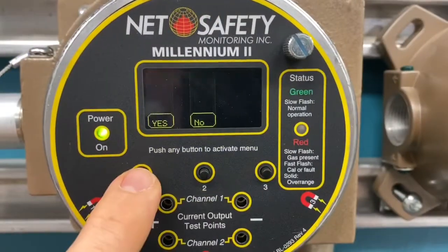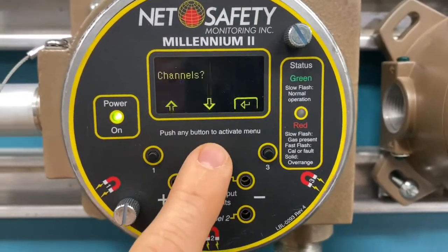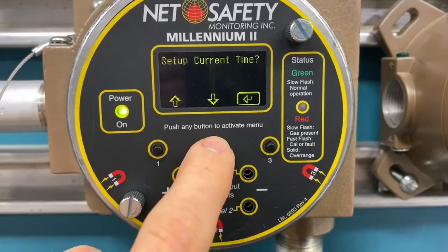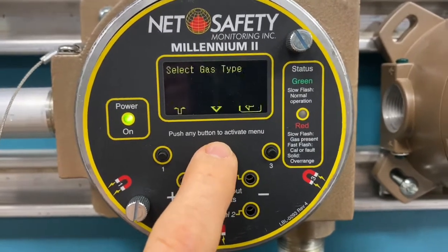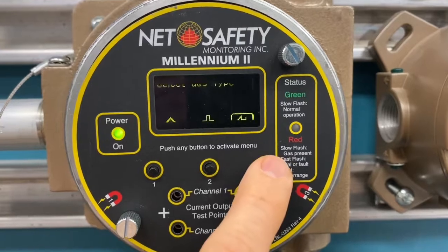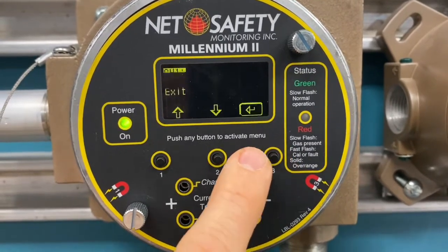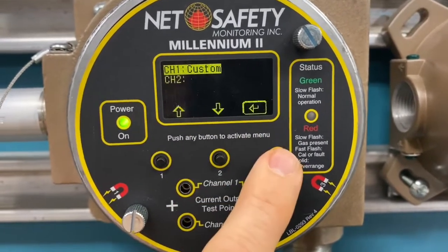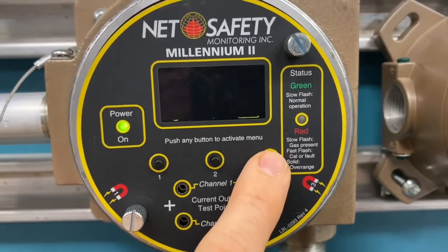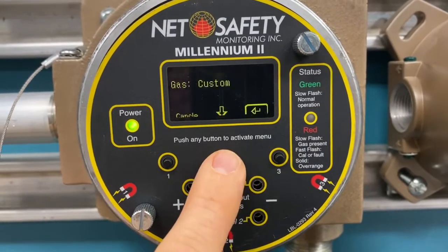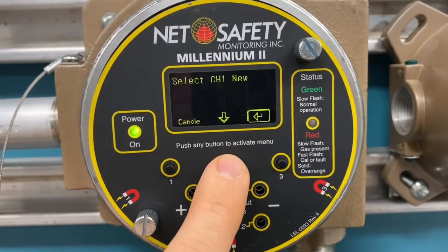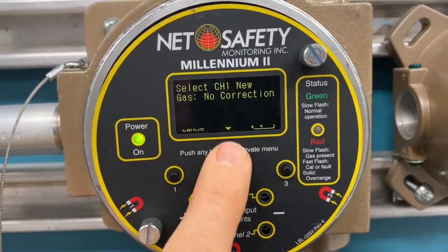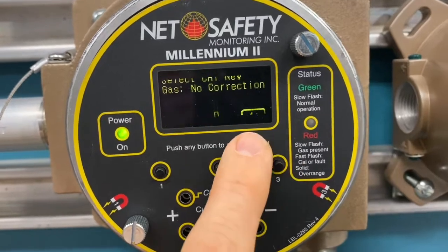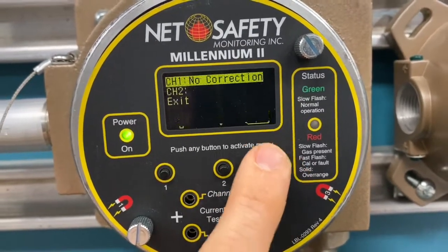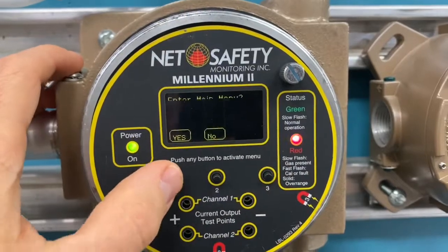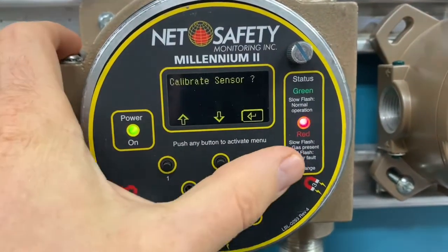All right, so before we calibrate, we just want to enter the main menu here, and we want to go down and make sure that the gas type here is set for channel 1. We want to make sure that it is set for no correction. So there, I had to push the down arrow here, change it to no correction, and we'll push number 3 for enter, and there it should read no correction.